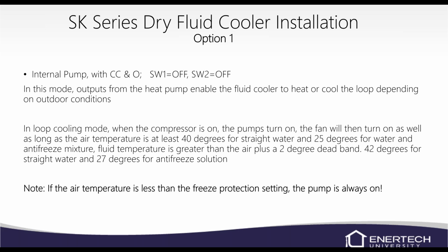So option 1, you've got an internal pump with your compressor contactor and O. In that situation, switch 1 is off, switch 2 is off. Basically in that mode, outputs from the heat pump enable the fluid cooler to heat or cool the loop. In loop cooling mode, when the compressor is on, the pumps turn on, then the fan will turn on as well, as long as the air temperature is at least 40 degrees for water and 25 degrees for water and antifreeze mixture. So that's your freeze protection settings. So you've got 25 degrees for water and antifreeze mixture and 40 degrees for straight water. Also, when the fluid temperature is greater than the air, plus 2 degree deadband. So 42 degrees for straight water and 27 degrees for antifreeze solution.